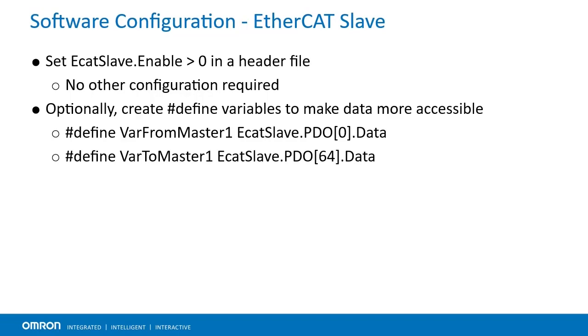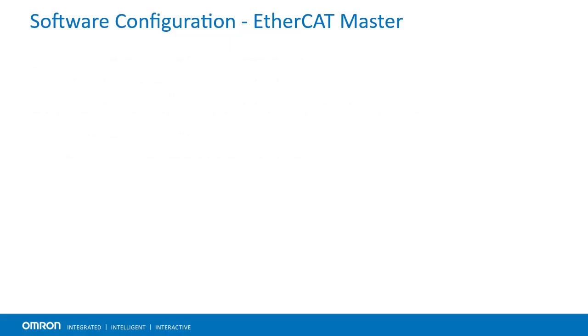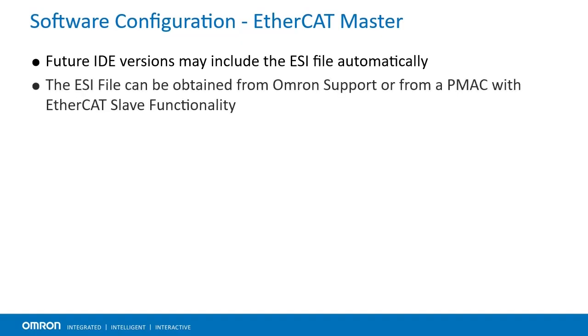Users can then create PLCs or other logic to copy data in and out of these registers. Configuring a master device to use PMAC as an EtherCAT Slave device is also fairly simple, as it is effectively the same as any other slave device. First, you will need to load your ESI file for the device. As of IDE version 4.5.2.9, it is not included by default, but the ESI file can be obtained by reaching out to your local OMRON support channel. It is also stored on the EtherCAT Slave device itself.